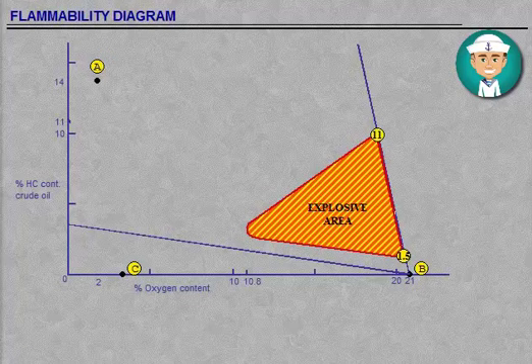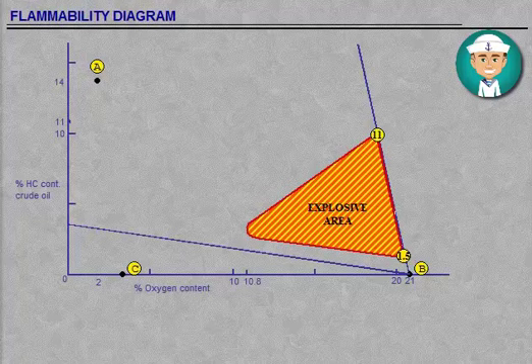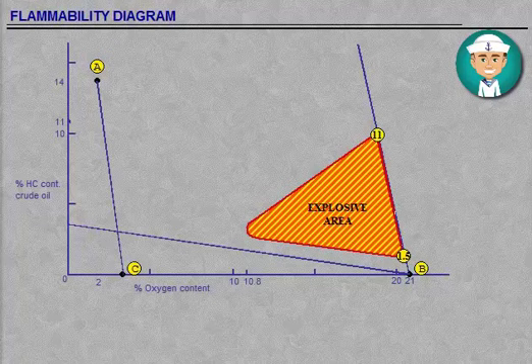Additionally, we have to supply more inert gas to decrease the oxygen content before any air venting can commence. As inerting continues, a line will extend from point A to point C, as long as the oxygen content in the supplied inert gas is 3% by volume.